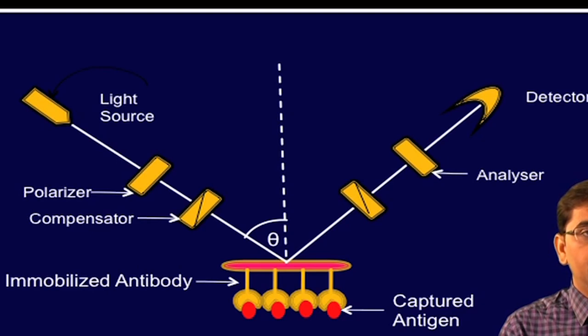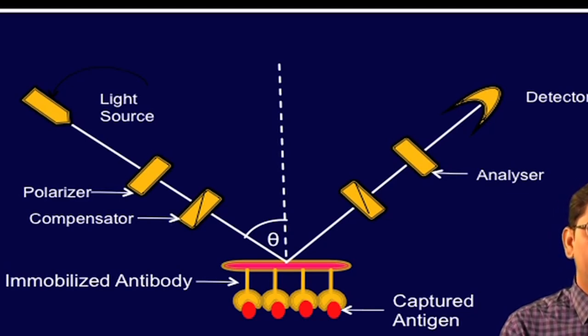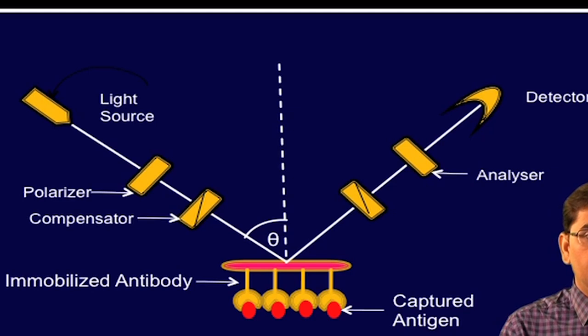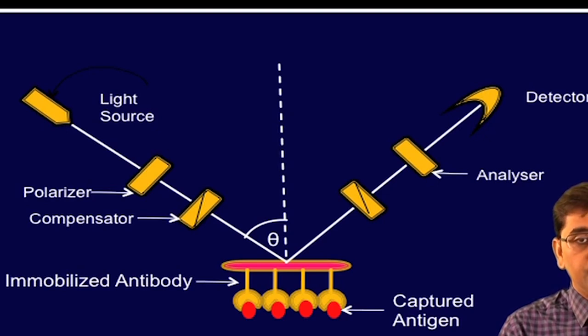A monochromatic laser light, linearly polarized by the polarizer, is passed through a compensator to produce elliptically polarized light. This light is reflected from the sample surface and again becomes linearly polarized, which is detected by an analyzer filter, and this reflected light intensity is monitored with a photo detector.